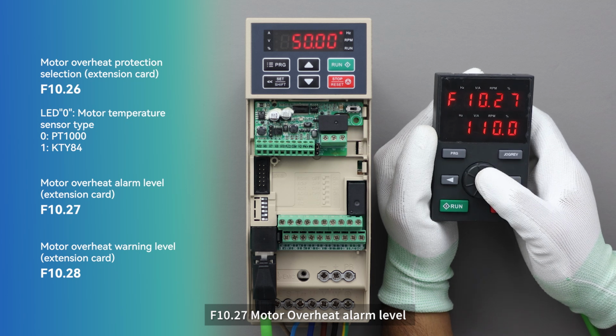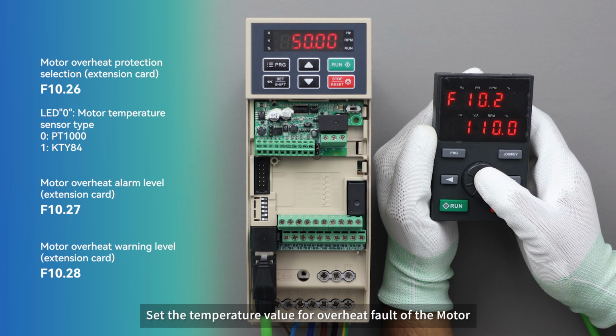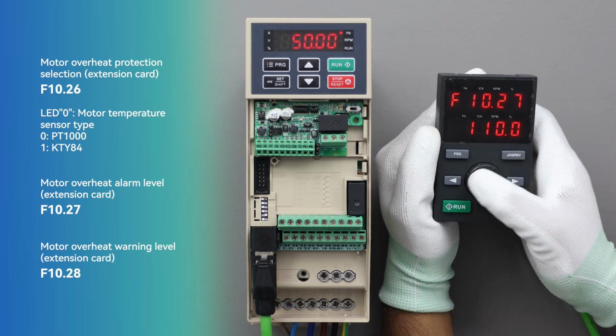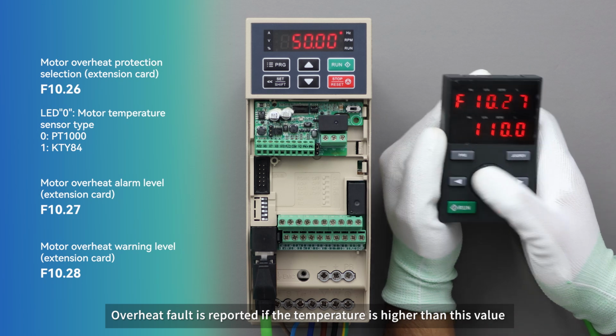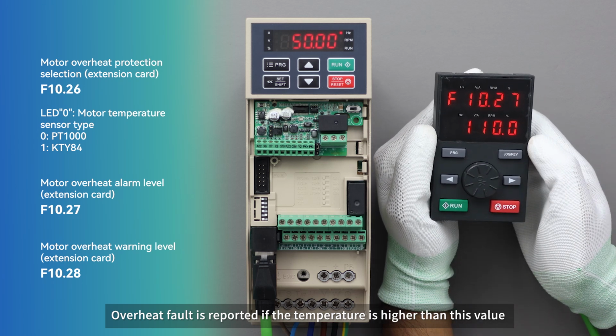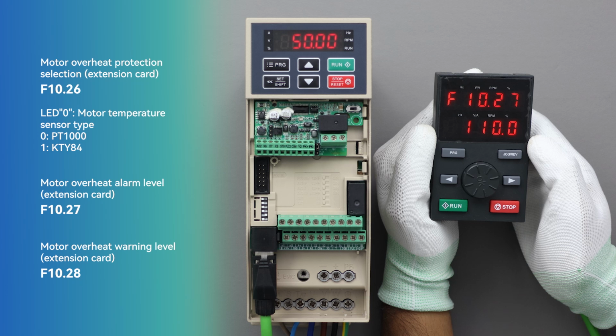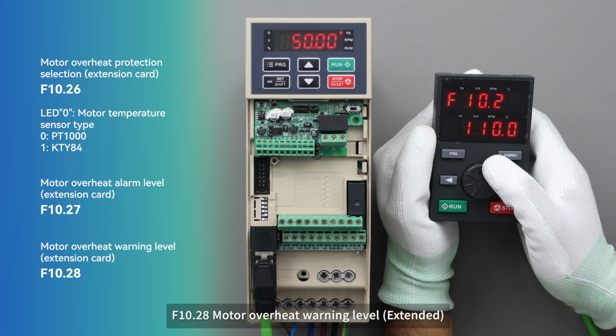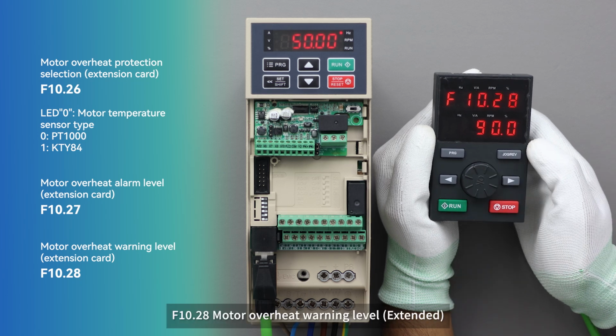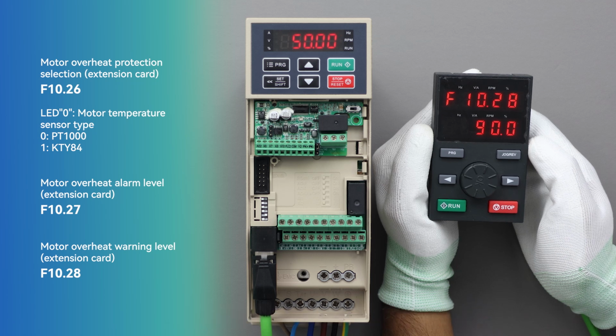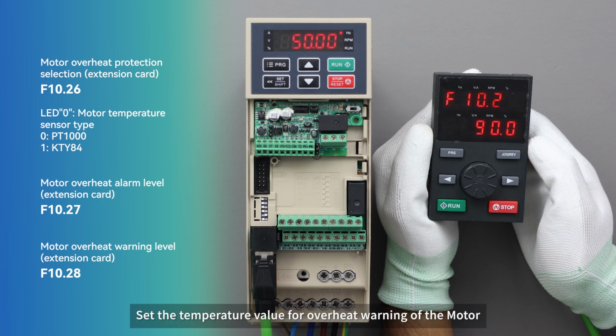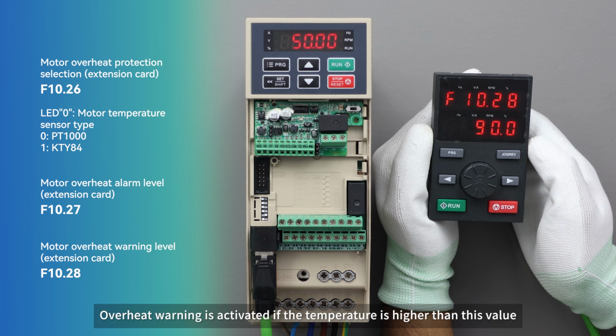F10.27 motor overheat alarm level. Set the temperature value for overheat fault of the motor. Overheat fault is reported if the temperature is higher than this value. F10.28 motor overheat warning level. Set the temperature value for overheat warning of the motor. Overheat warning is activated if the temperature is higher than this value.